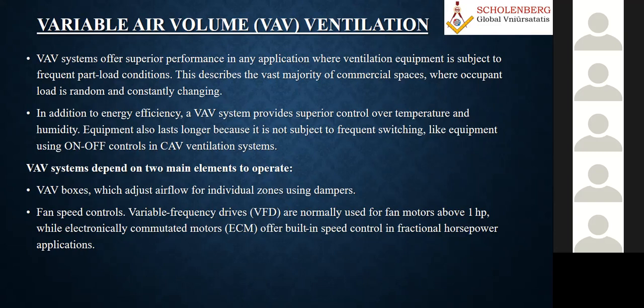But again, what is the VAV system? It depends upon 2 major elements. One is the VAV boxes, which I told you are the VAV terminals, and then in the VAV boxes we have fan controls. Depending upon the VFDs, variable frequency drives, normally used for fan motors above 1 horsepower. Basically for higher ratings we always use VFDs. But at the terminal level there will also be small fans, and for those we use electronically commutated motors, ECM.